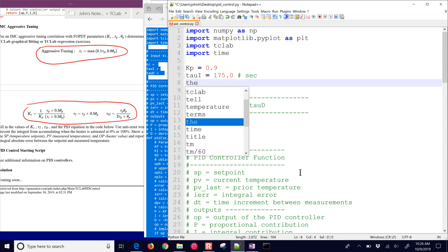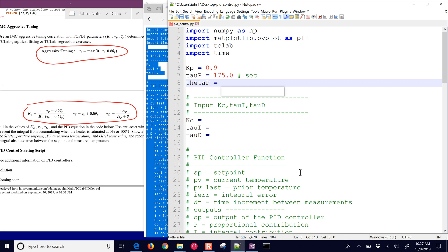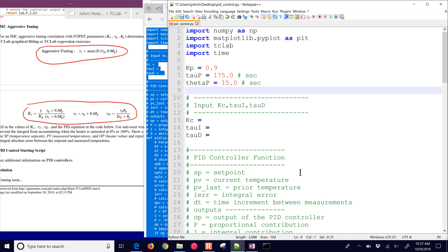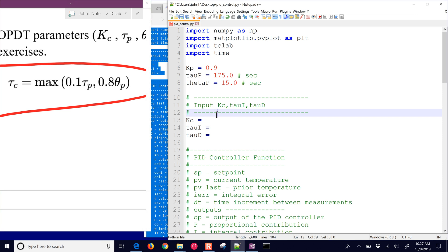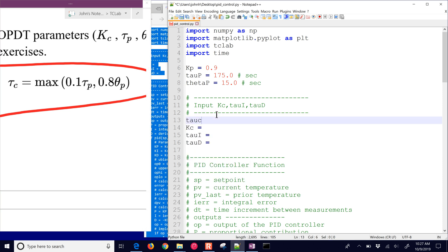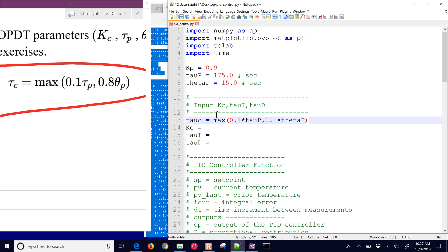We had tau_P and theta_P, where theta_P is about 15 seconds. That's our approximate first-order plus dead-time model. We're going to start with the aggressive tuning, so we need a tau_C value: tau_C equals the max of 0.1 times tau_P and 0.8 times theta_P. So 0.1 times tau_P is about 17.5, versus 0.8 times theta_P which is about 11, so tau_C will be about 17.5.